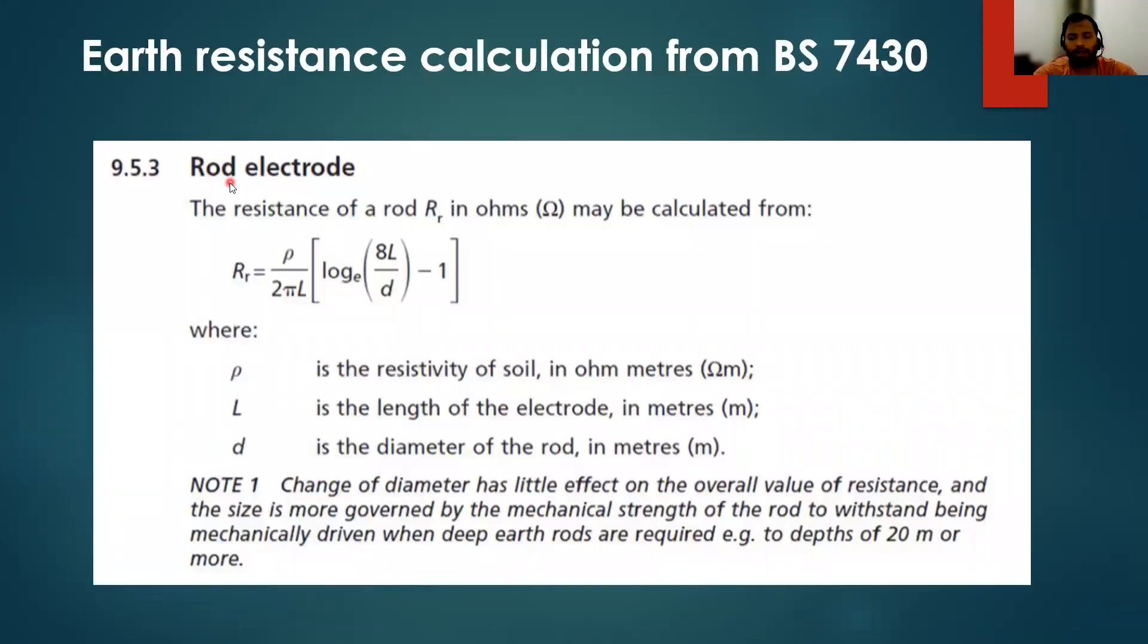How to calculate the resistance of earth rod? According to BS 7430 standards, earth rod formula: Rr = ρ/(2πL) × [log(8L/D) - 1]. In this formula, where ρ is equal to resistivity of soil, L is equal to length of electrode, D is the diameter of the rod. Basically, these three parameters will decide the earth rod resistance.